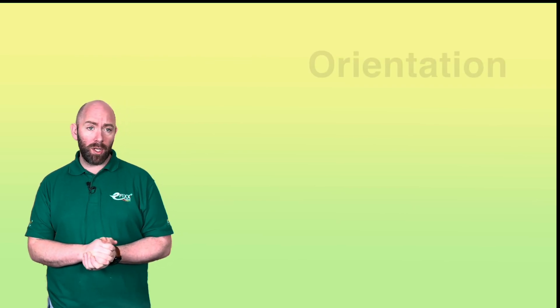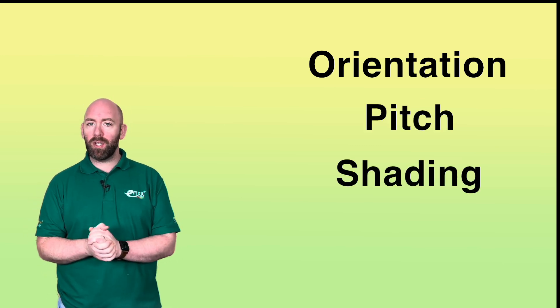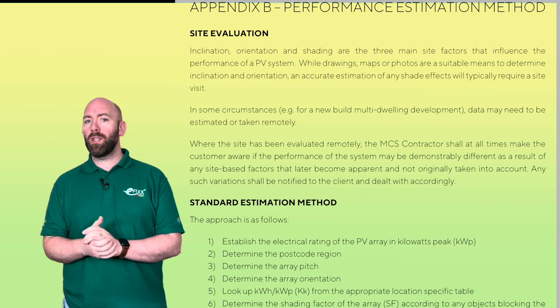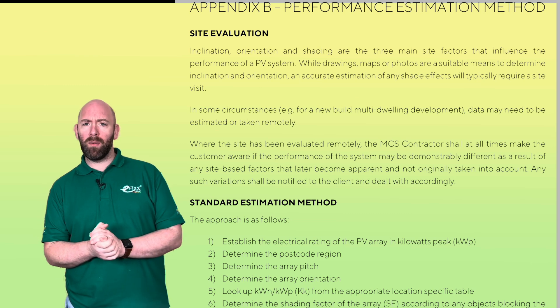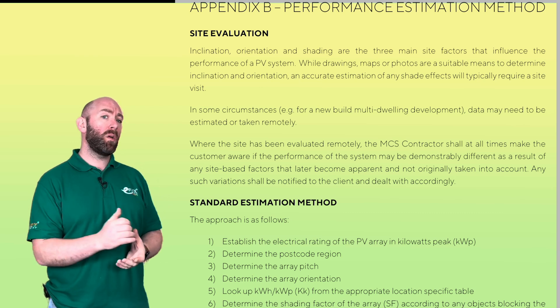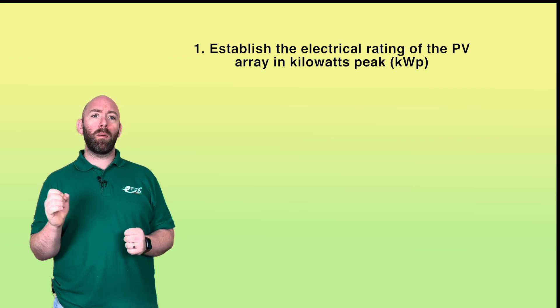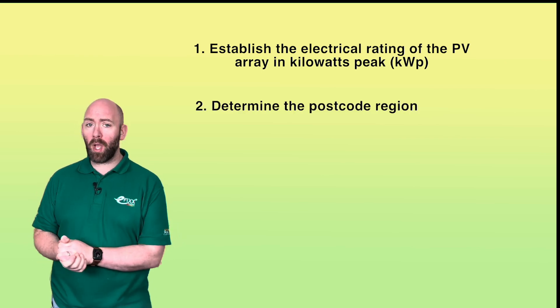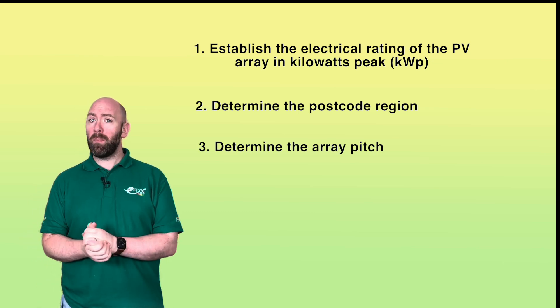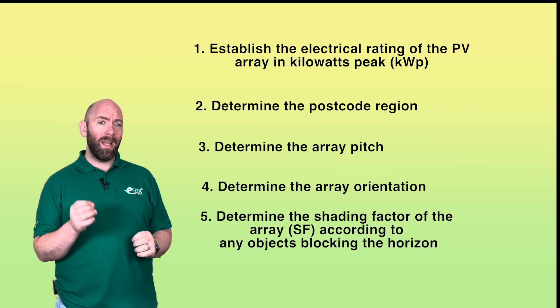Calculating the annual electrical generation from the PV array brings us back to the three main factors: orientation, pitch, and shading. The MCS document MIS 3002, appendix B, gives us a performance estimation method to follow. By standardising this process it makes it easier for solar installers to provide pre-sale information to customers. The five steps are: 1. Work out the rating of the PV array in kilowatt peak. 2. Ascertain the postcode region. 3. Determine the pitch of the array. 4. Determine the orientation of the array. And 5. Assess any shading. Remember, these are estimated figures and it's important to inform the customer of this.